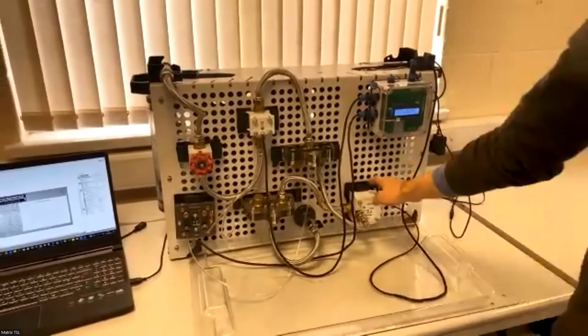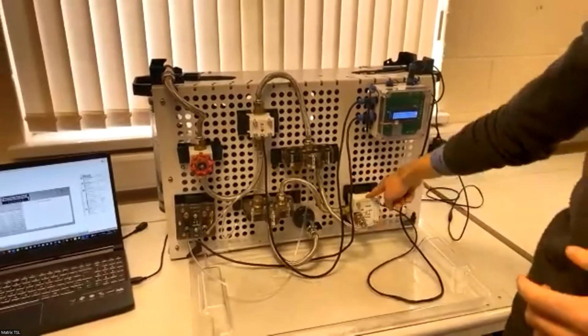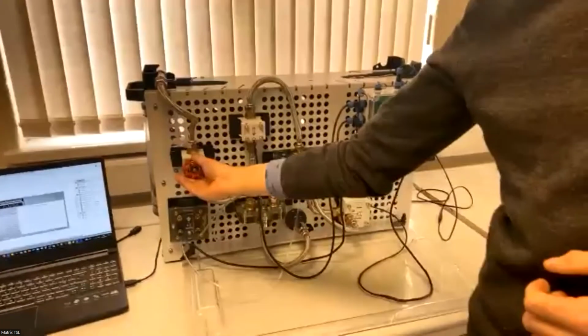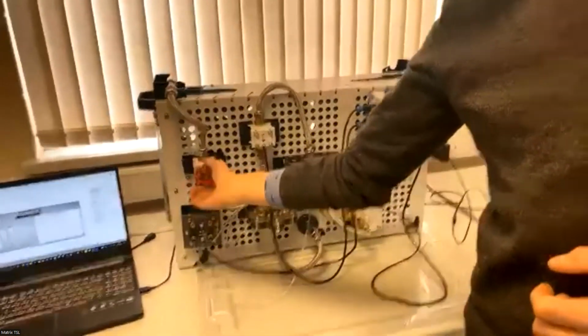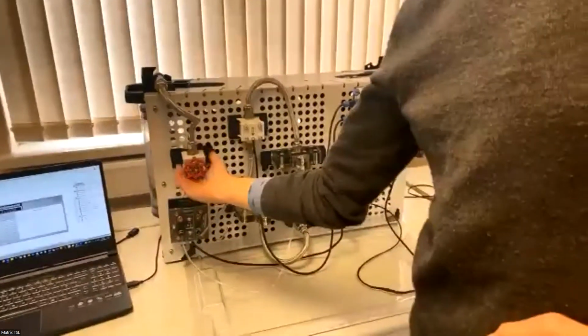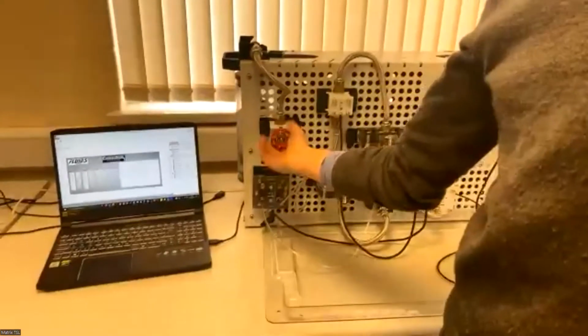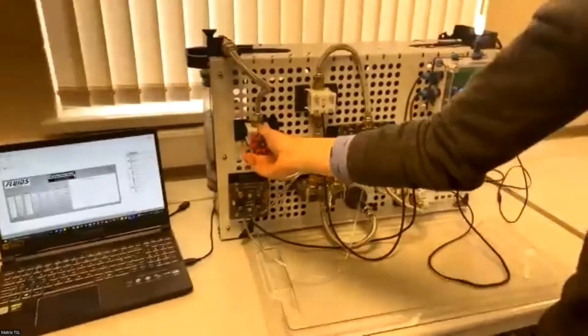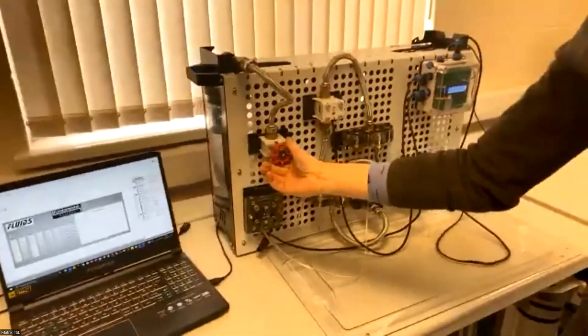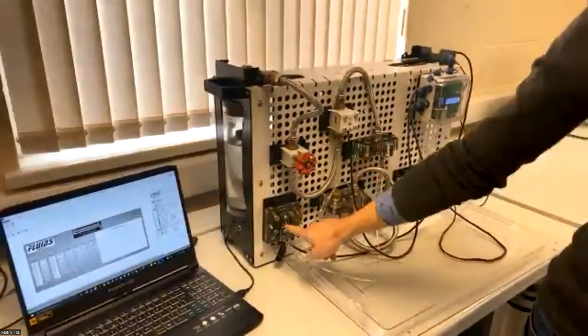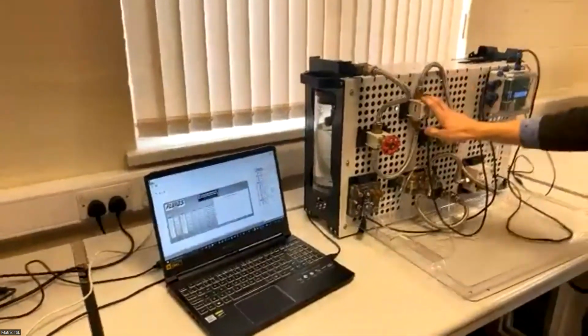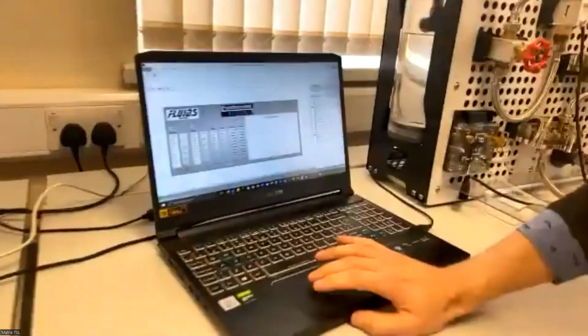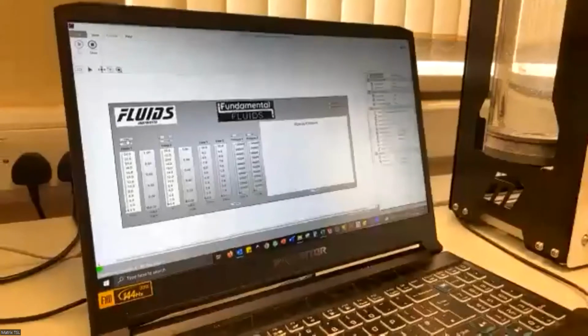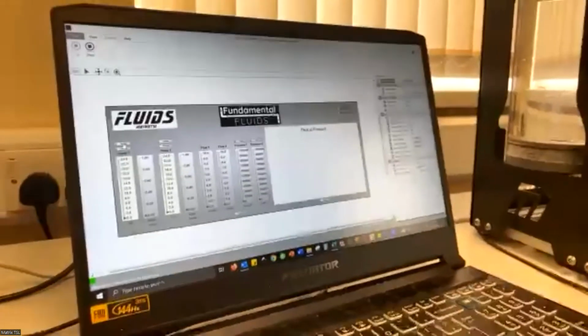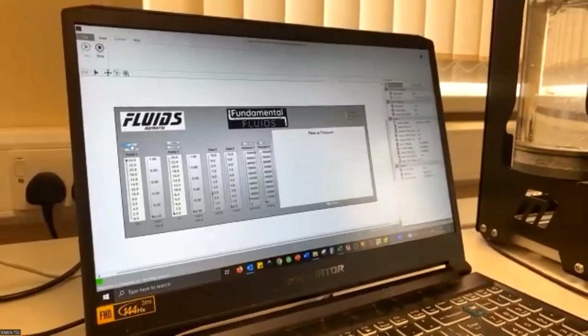As Liam said previously, we're going to sweep down from 24 volts. Initially we'll have this fully open and see the behavior of the pump. We'll be measuring differential pressure before and after, and also flow rate, so we should be able to plot pressure versus flow. That's done automatically within the software, as you can see.